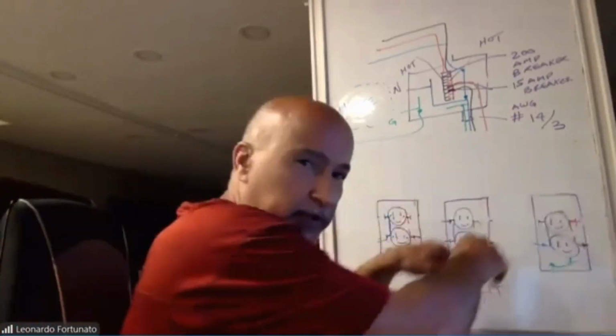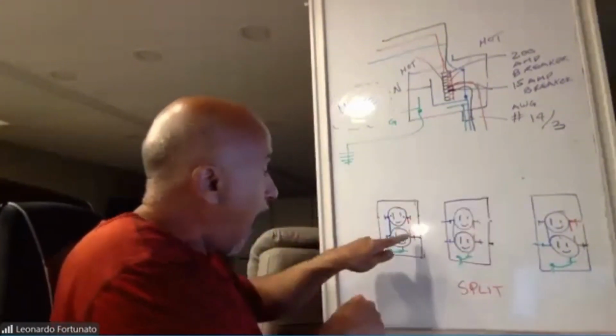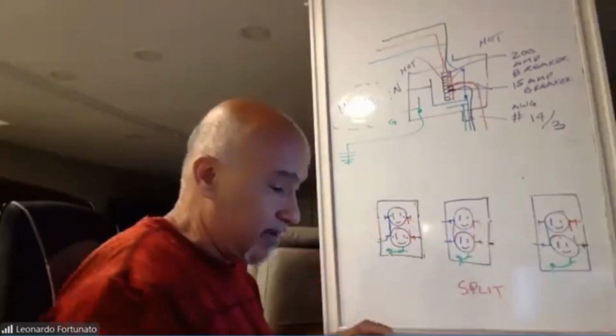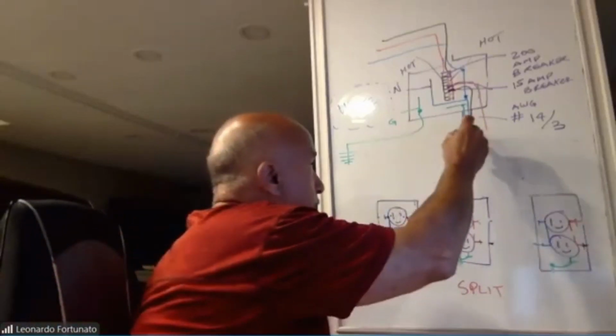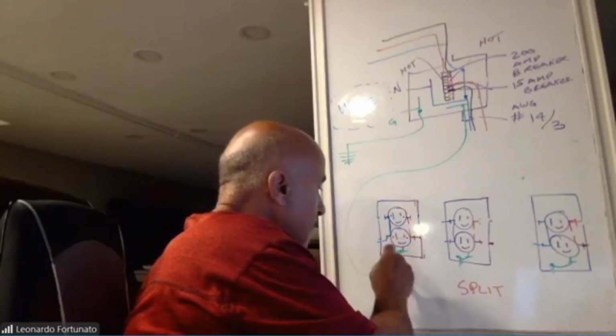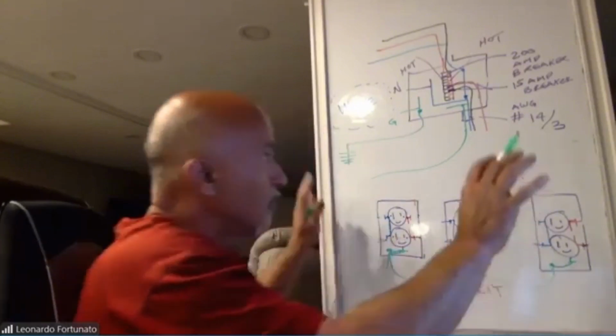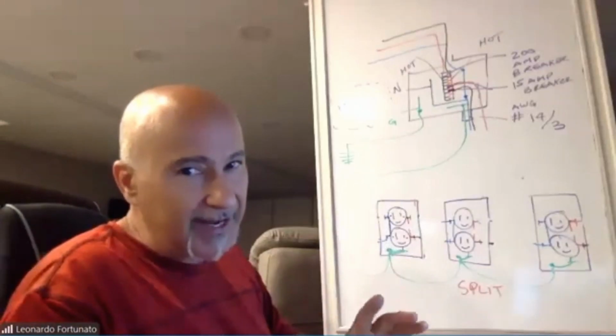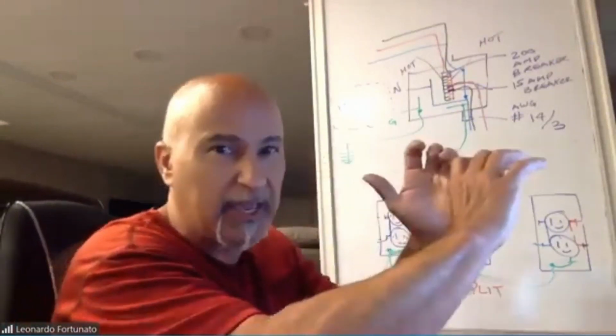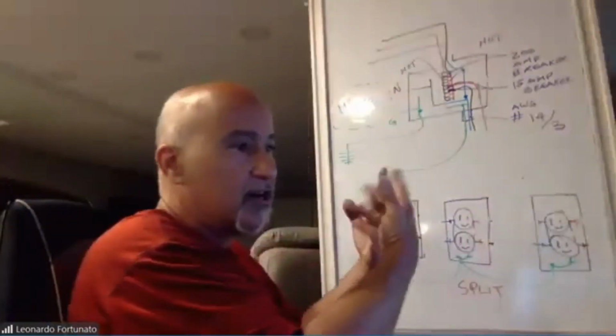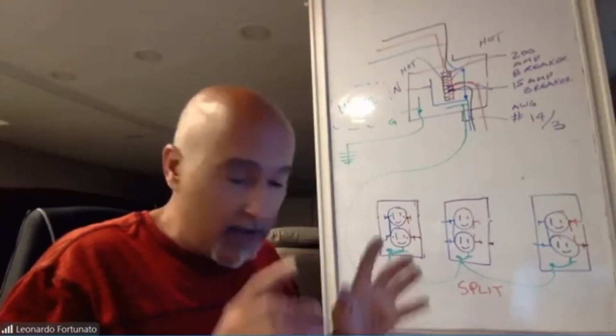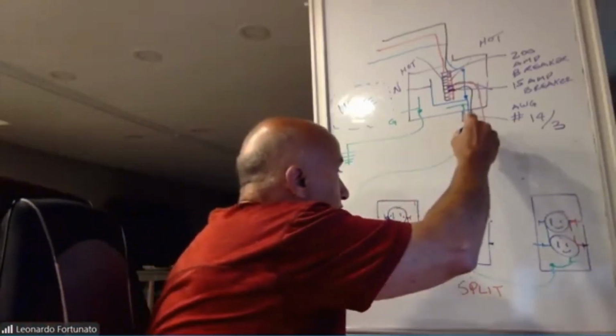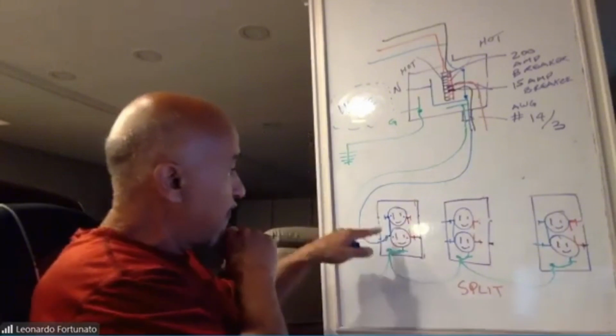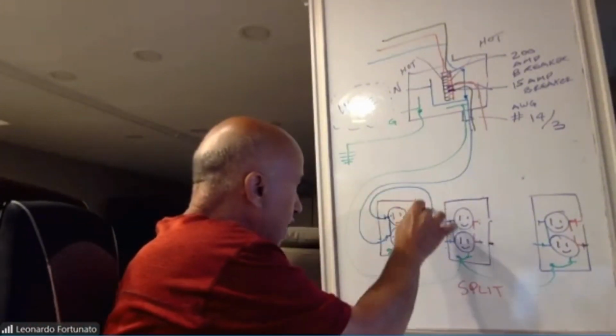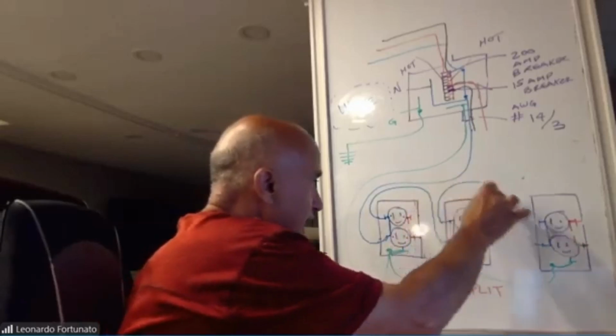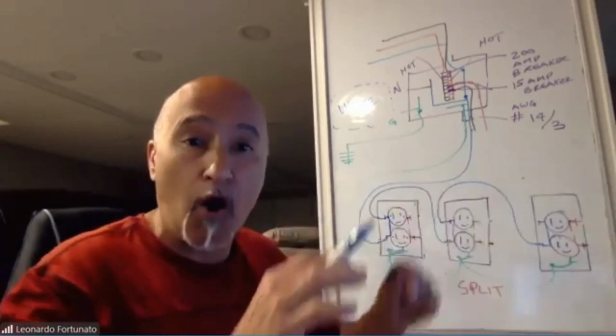Again, using 14-3, let's wire this in series now. I've got all 3 of these already split. Here is the ground wire. The ground comes here and jumps, comes here and jumps, from there and jumps. We've taken care of the ground. Again, keep in mind, ladies and gentlemen, all our conductors are in the same cable. I'm just showing you this in a quick fashion to show you the connections. Here is my neutral. Here's the neutral. It comes in. I go over here. From here, I'm going to come out over here with my neutral. I come in here. From here, I leave and I come in here. My neutral is connected to all 3 receptacles now.